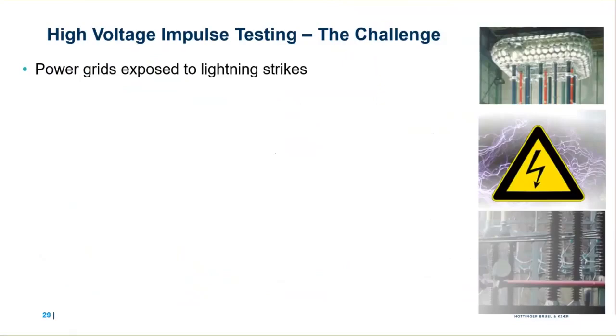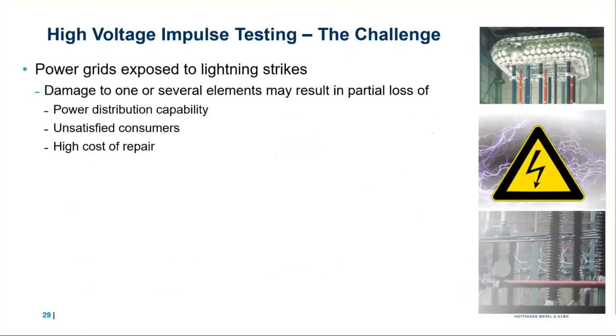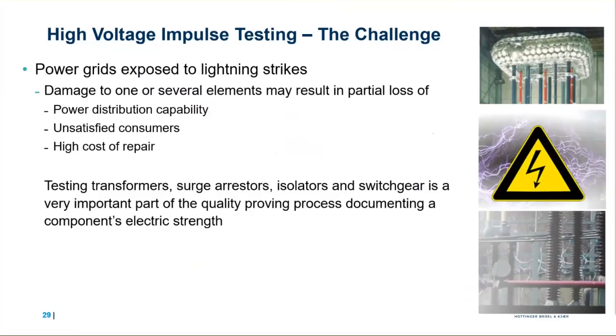Our next application is high voltage impulse testing. In this application, the challenge is that power grids are exposed to lightning strikes. So you've got damage to one or several elements that may result in a partial loss of power distribution, unsatisfied customers, and a high cost of repair.